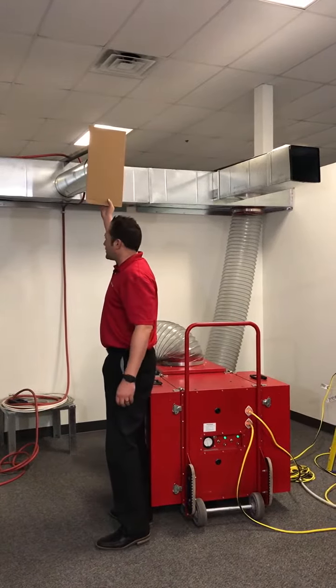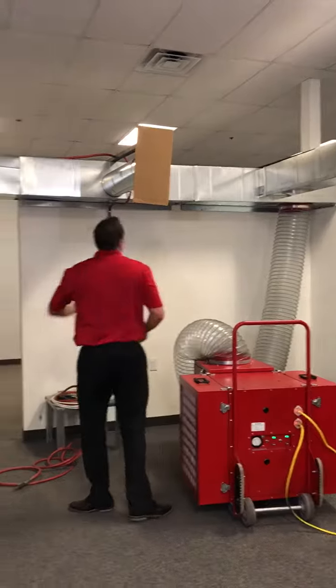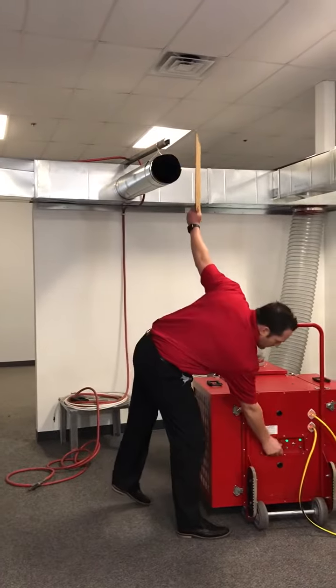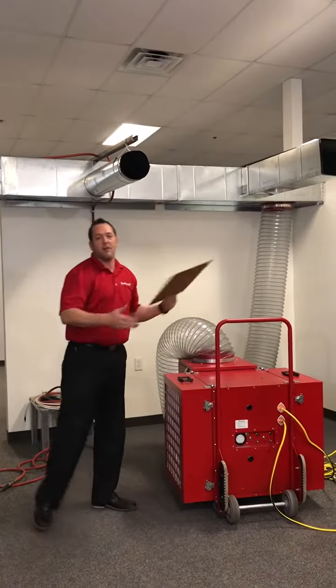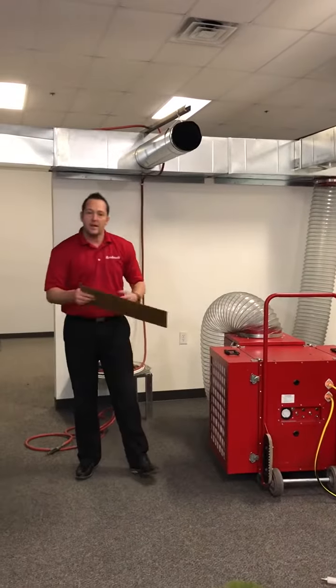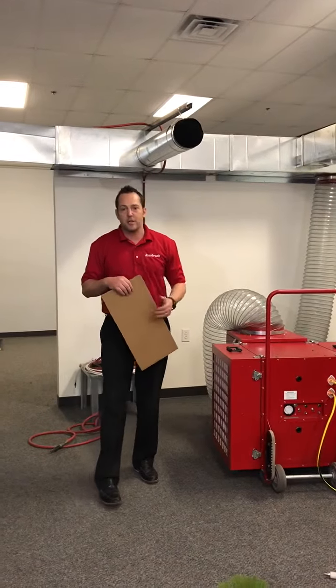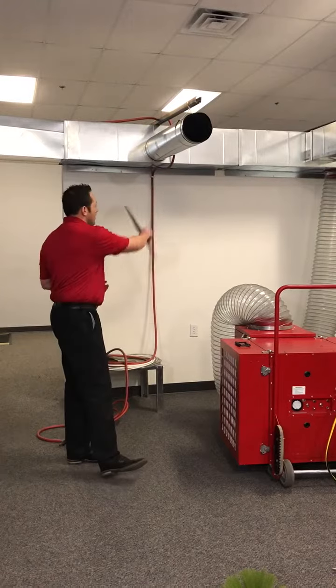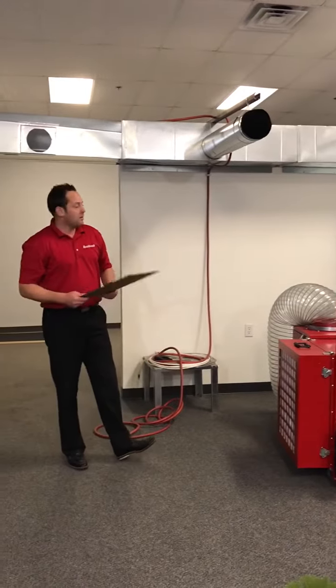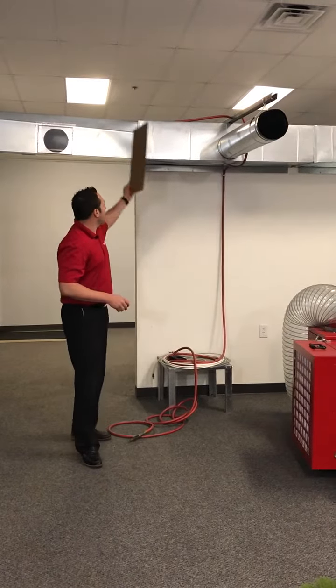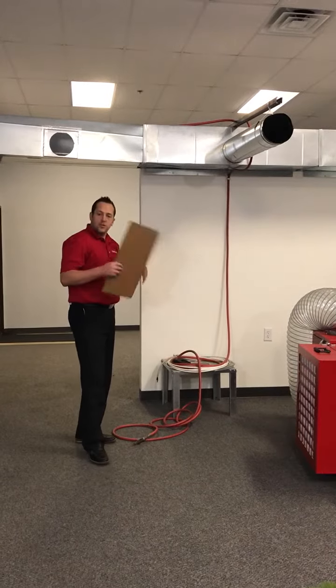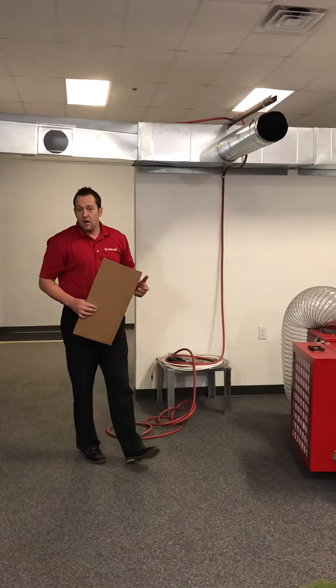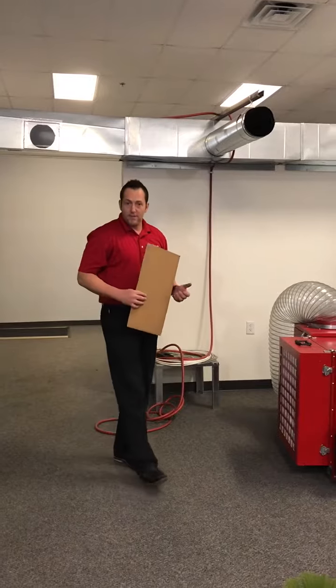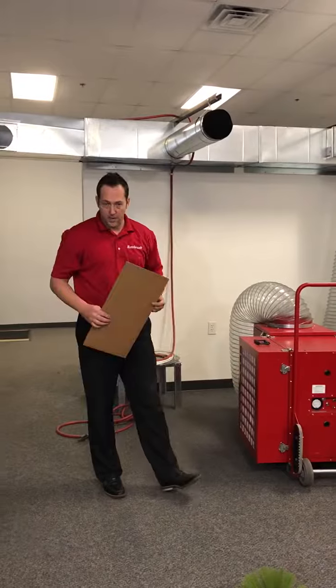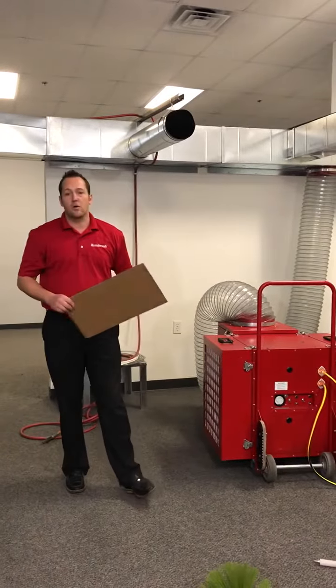Depending on how large or small the ductwork is, you can go through and seal off multiple registers inside of the home. Now, if you're cleaning a commercial or industrial application, and your ductwork is 3 times this size, you'll take these zone bags and go off and actually zone them off. The smaller the area that you're cleaning, the more airflow you're going to maximize as you seal off these different registers.